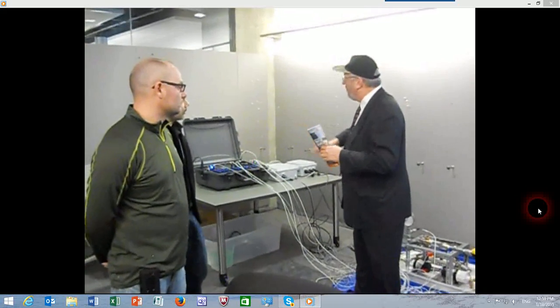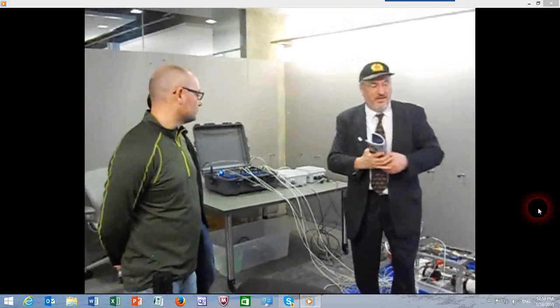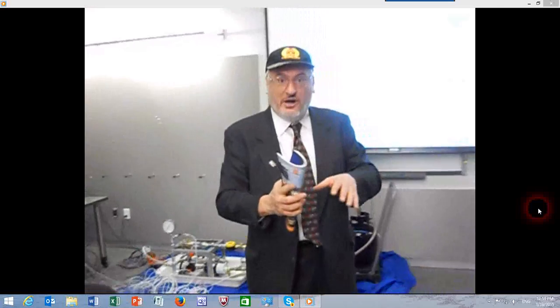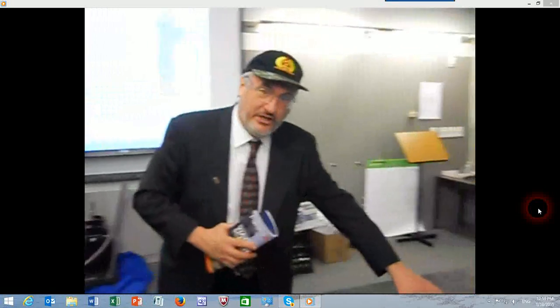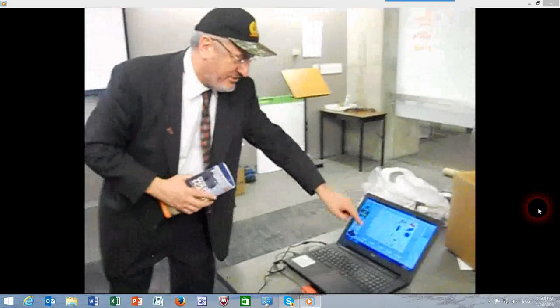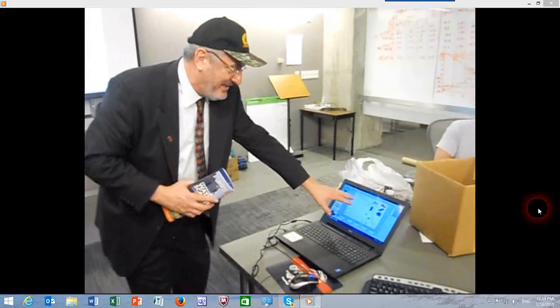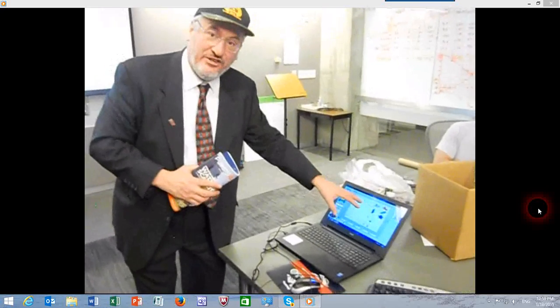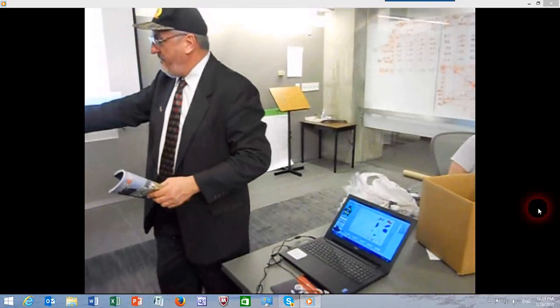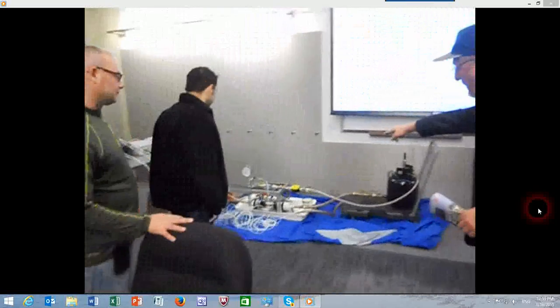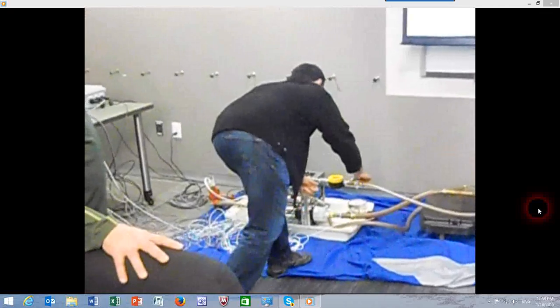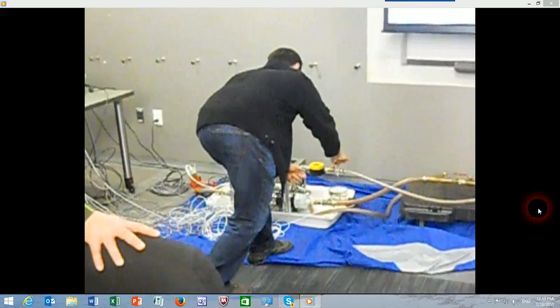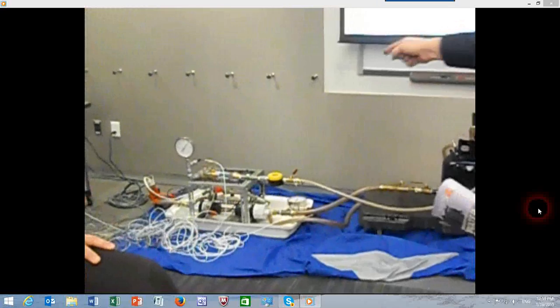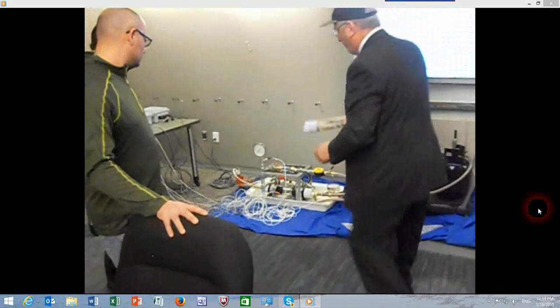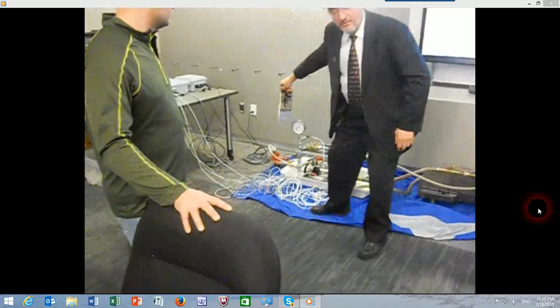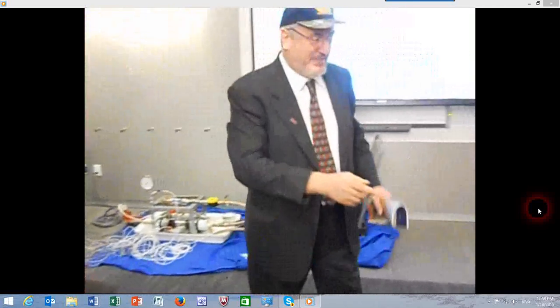So when that system is going to the cell tower, it comes back here, and locally, imagine now you are at the office at a computer. You're looking at the computer screen here, which shows head capacity, efficiency, and power curve as is, and all these dots are points during the operation. If I turn the valve, Jim, if you can circle the valve a little bit on the discharge side. Let's say operations wants less flow, so the flow will change. That flow now gets picked up, and the pressure, flow, and amps. By the way, I didn't mention the amps, the power also gets measured, the red clamp wire shown there.